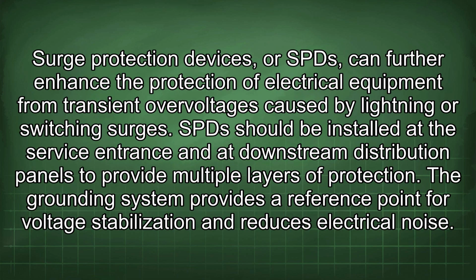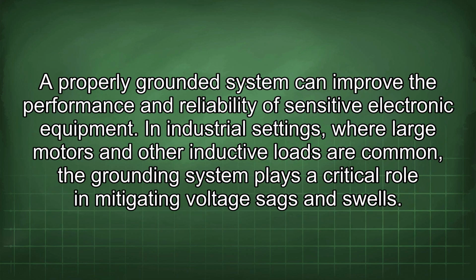Surge protection devices, or SPDs, can further enhance the protection of electrical equipment from transient overvoltages caused by lightning or switching surges. SPDs should be installed at the service entrance and at downstream distribution panels to provide multiple layers of protection. The grounding system provides a reference point for voltage stabilization and reduces electrical noise. A properly grounded system can improve the performance and reliability of sensitive electronic equipment.